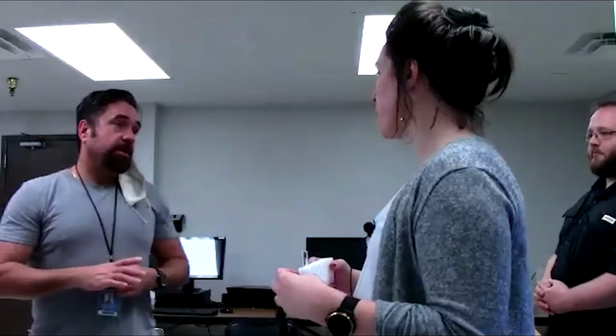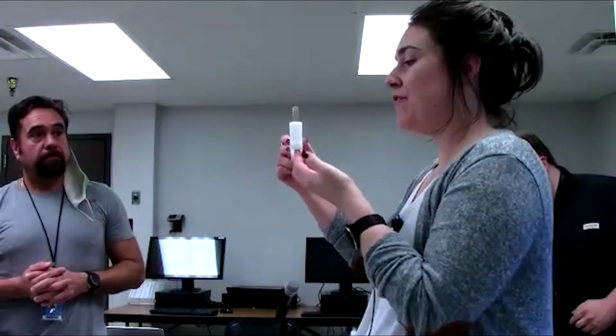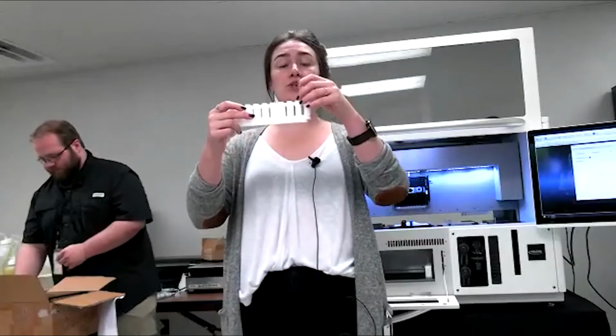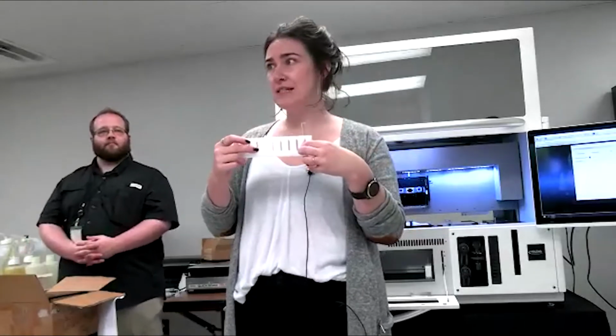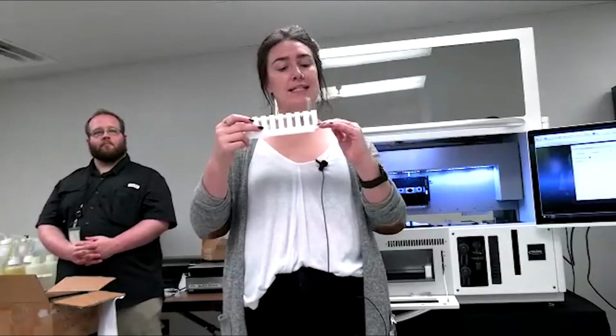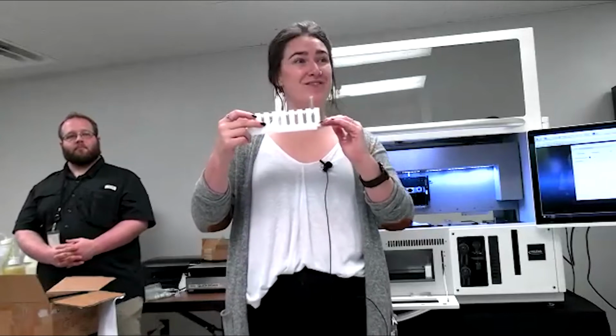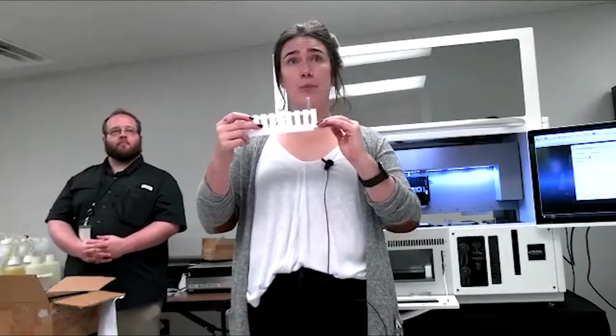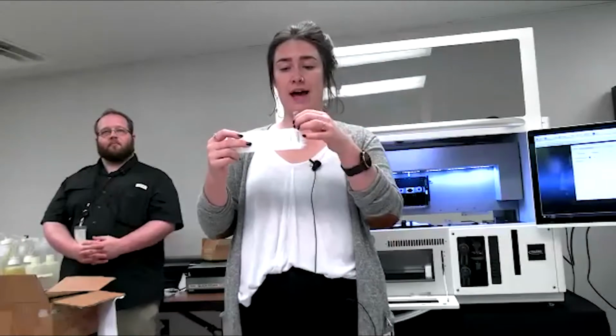There was a question today from a customer about changing the minimum volume, the hold-up volume of the tube. That's set. We can't change that. We're at the tolerance of our current system. Yeah, so you actually calibrate to the calculated height of the very bottom of one of these tubes. So your pipette is automatically going to go to the very bottom of the tube to get sample. It won't always, it'll stop when it detects fluid, but let's say you have a very small amount of fluid in there, it'll go to the point that it is calculated that you need that much sample to proceed. But if it doesn't find it at that point, it will plunge to the bottom of the tube and aspirate anyway to try to get anything out of that tube that it can get.